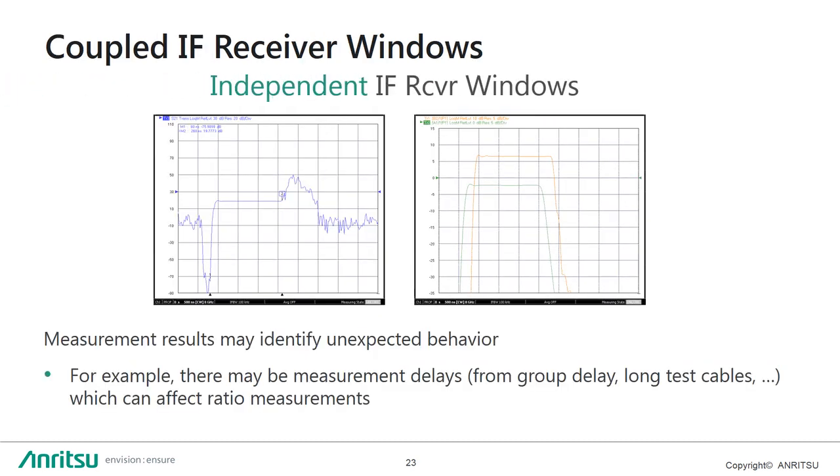So why is it necessary to have a lot of flexibility in the setup? Well, sometimes we get unexpected results. So above is a pulsed S parameter measurement that we are trying to make over this time frame. Flat pass of the left hand side trace. There may be some delays or timing issues due to the external cables, etc. And this is where PulseView helps us out a lot.